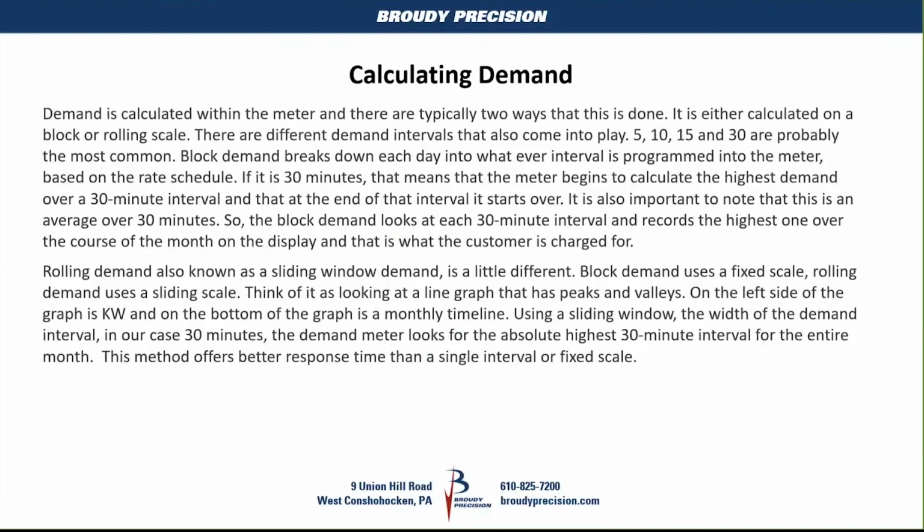That could come in as a pulse. That could come in as on our meters that we sell. The rate at which the kilowatts are consumed in the building begins to increase based upon how much equipment is being used. At the end of that half an hour interval, it starts all over again. So you reset the clock, or the counter, I should say, and it starts counting all over again.